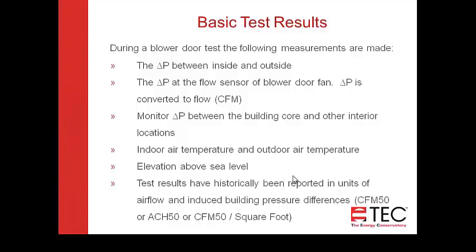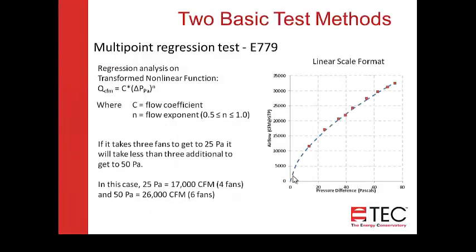Test results have historically been reported in units of airflow and induced pressure differences. The most common ones: results reported in CFM50 or air changes per hour at 50, or CFM per square foot of floor area, or potentially at a different pressure such as 75 pascals. There are two basic test methods. The first is multipoint regression — ASTM E779 — which does regression analysis using the formula for flow: Q equals a flow coefficient times the change in pressure raised to the N flow exponent.